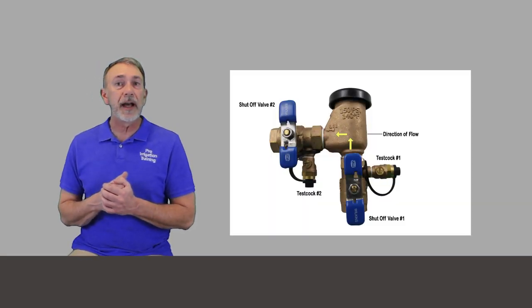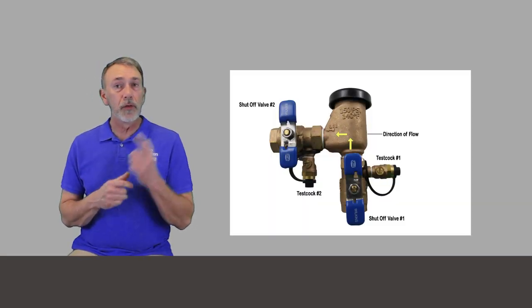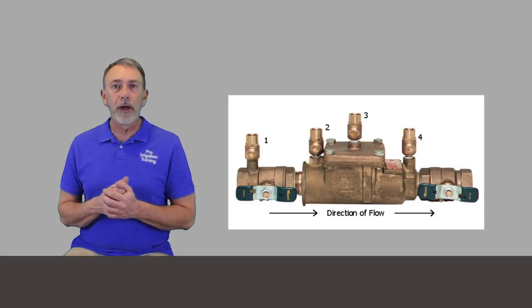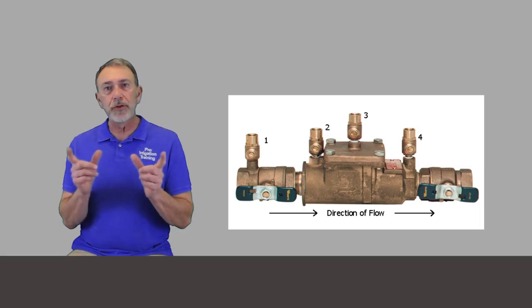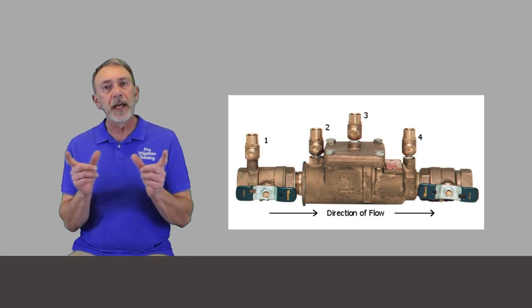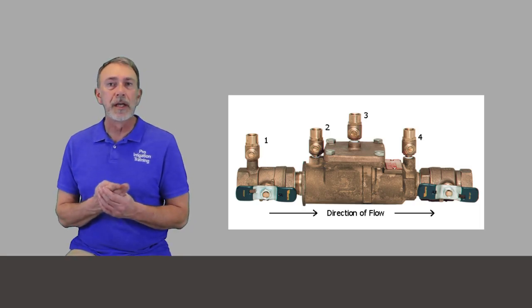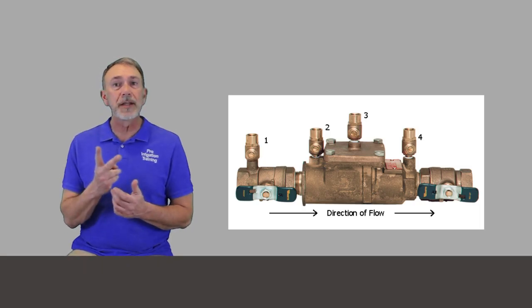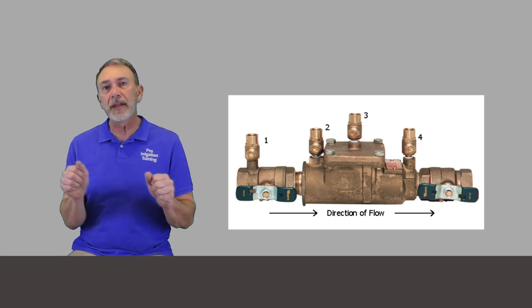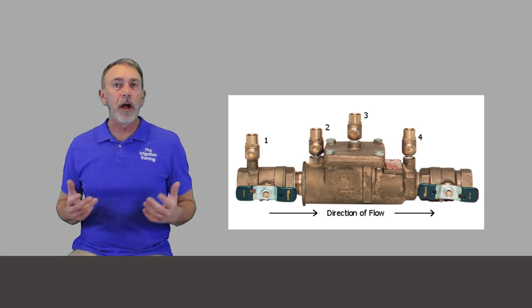And generally you'll have a test cock before and after each of your check valves. For instance, a pressure vacuum breaker, they'll only be one valve there. But on a double check valve or an RP, you have two check valve setups or you'll generally have four test cocks and two isolation valves, a valve on each side of the issue.